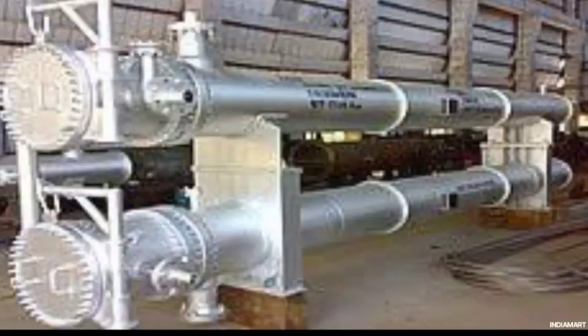That's why we transfer the seismic weight of the equipment to the bottom at that time. But for pull out, do you verify for bottom or top? Worst condition - for pull out, I check for the top, because for the top, the length from center to center to the bottom is quite high, so the force becomes high. If your top bundle is pulling out easily, your bottom bundle will pull out easily too.